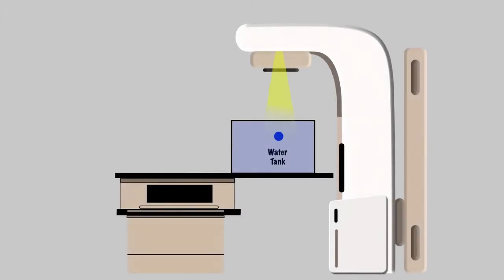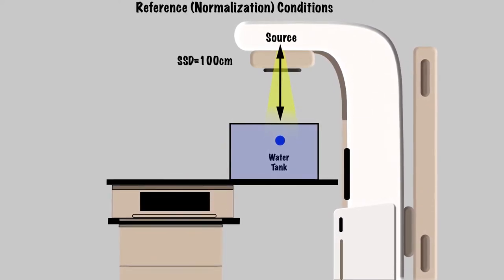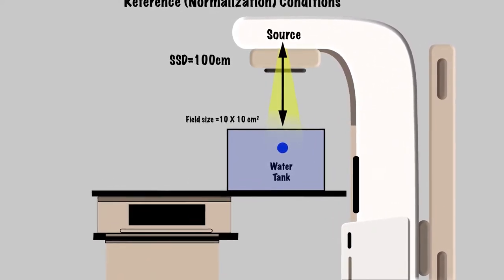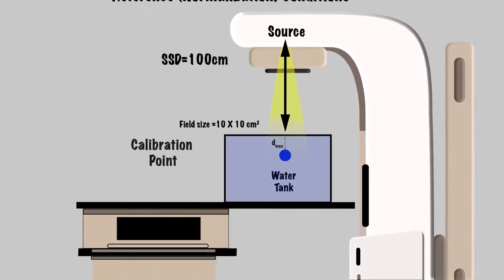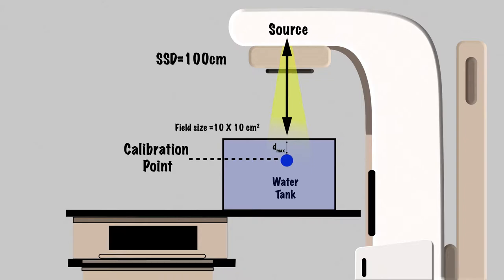In the last video, we talked about the factors affecting dose calculations and the reference or normalization conditions typically used to calibrate a LINAC. These include an SSD of 100 centimeters, a field size of 10 by 10 centimeters, and the calibration point at D max. The machine is calibrated to deliver one centigray per monitor unit to the reference calibration point for each individual beam energy.